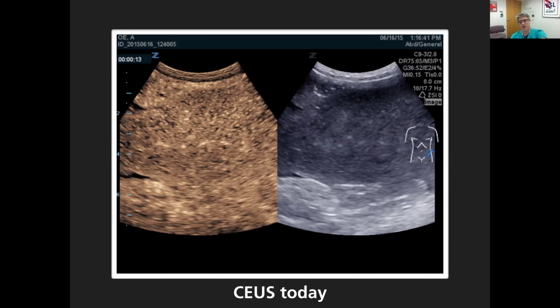B-mode image. And the reason that's so degraded, looks so fuzzy, is that you have to keep the MI low so as not to burst the bubbles. So if you look at the right side, the MI is 0.15, which is way lower than what we usually use. So typically, for any contrast imaging, you would do normal B-mode first and then go into contrast mode, because the B-mode is just for your orientation, and you probably don't get much detail with the B-mode image with that.